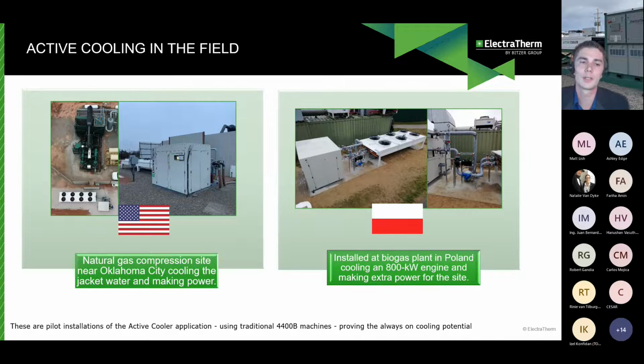So it does illustrate that it is possible to remove the jacket water circuit from those radiators or coolers and eliminate a lot of that parasitic load there. There's also potential to free up horsepower in those applications, but sites with electric fans, you're offsetting the need for that load as well. So I talked about, okay, we're making power with the active cooler, but we're also eliminating a parasitic load of your existing cooling source, whether that's horsepower or whether that is actually electricity for electric coolers. You have that benefit as well.